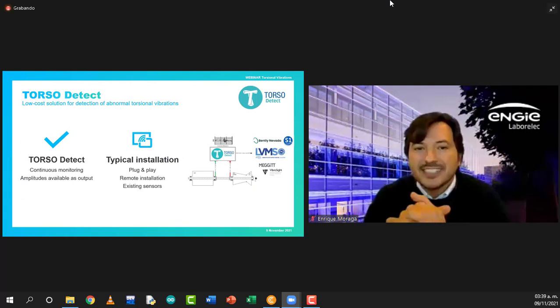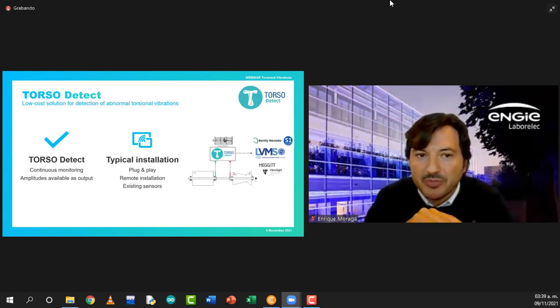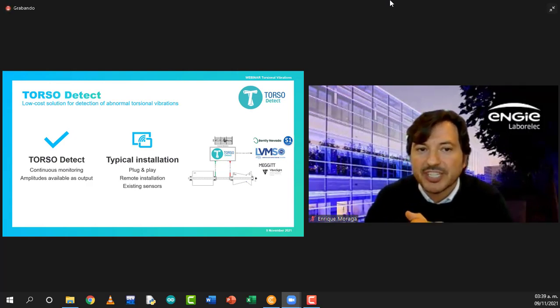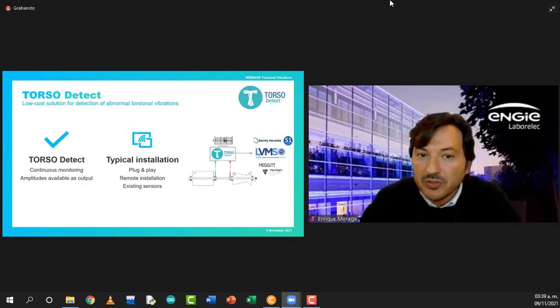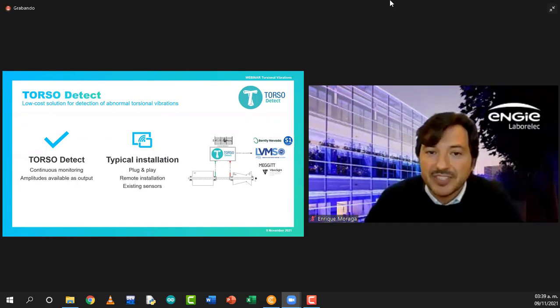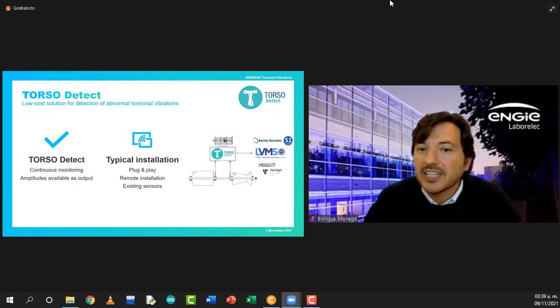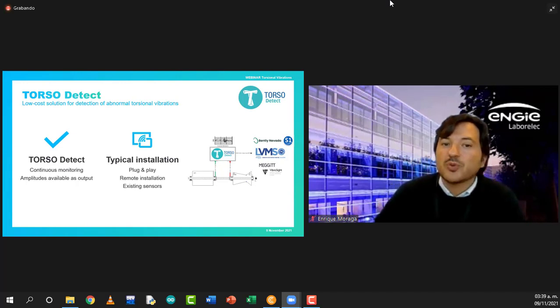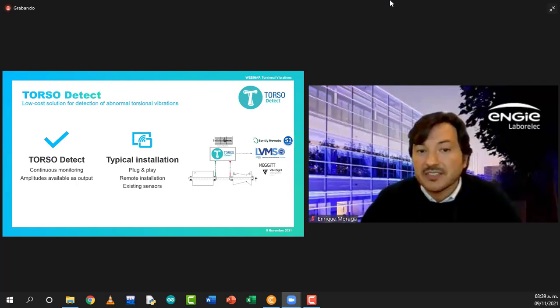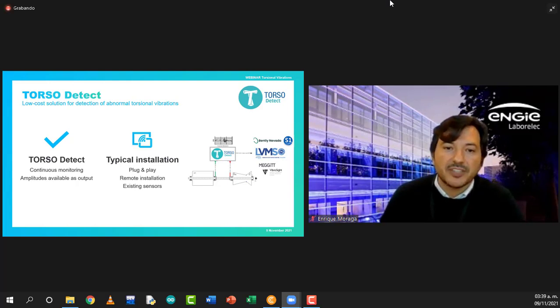Well, Torso Detect is a low-cost solution for detection of abnormal torsional vibration. It shares many of the characteristics of Torso Protect. In this case, the device is continuous monitoring of torsional vibrations. The torsional vibration amplitude is easily integrated into the DCS or in a general monitoring system, which is already installed in the power plant, like System 1 of Bentley Nevada or others. Regarding the installation, it is really simple, plug and play, that can be easily installed by the power plant operator and supported by us remotely. Unlike Torso Protect, existing sensors can be used, and no new sensors need to be installed, thanks to the galvanic isolation and signal conditioning previously explained.